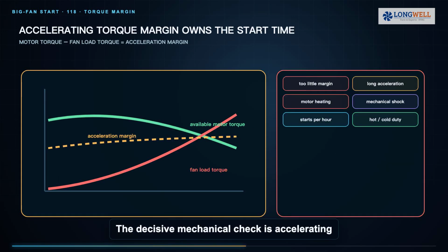The decisive mechanical check is accelerating torque margin across the entire speed range. Subtract fan load torque from available motor torque. The remaining margin accelerates the inertia. Too little margin lengthens the start and increases heating. Too much abrupt torque can stress couplings, belts, mounts, and duct structures. Verify allowable starts per hour and hot versus cold starting duty.